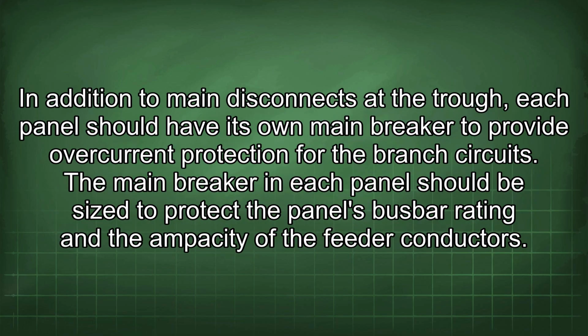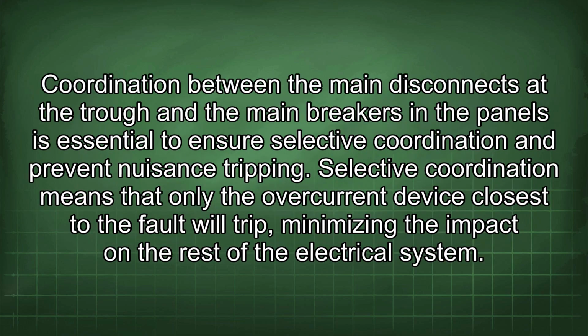In addition to main disconnects at the trough, each panel should have its own main breaker to provide overcurrent protection for the branch circuits. The main breaker in each panel should be sized to protect the panel's busbar rating and the ampacity of the feeder conductors. Coordination between the main disconnects at the trough and the main breakers in the panels is essential to ensure selective coordination and prevent nuisance tripping. Selective coordination means that only the overcurrent device closest to the fault will trip, minimizing the impact on the rest of the electrical system.